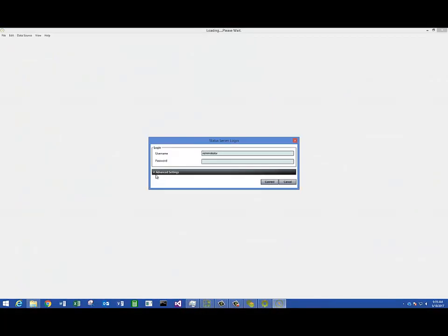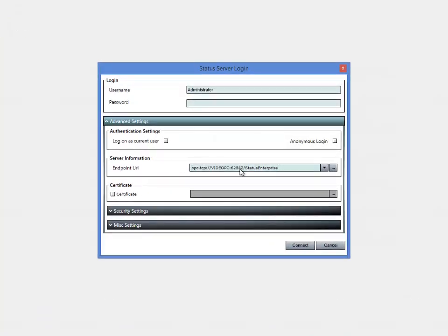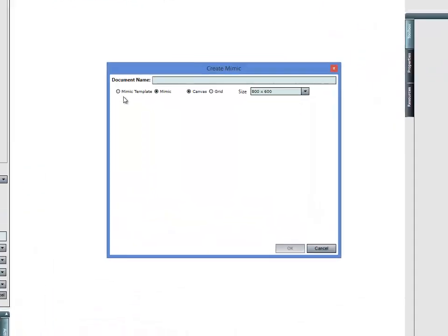BSCADA has the best graphics design experience in the industry. We're going to launch our Mimic Designer and connect up to Status Enterprise. The first thing we're going to do is create a new Mimic. I can create a couple of different types of Mimics: a regular Mimic, or a Mimic Template. A Mimic Template is when you create a Mimic for a type of thing — I could create one Mimic for a pump and use that Mimic with every pump in my system, so I only have to do one screen and get complete reuse. This is where the power of the model becomes available to us — having that model well defined allows us to get reuse within the software. But I'm just going to create a regular Mimic right now and call it Test.